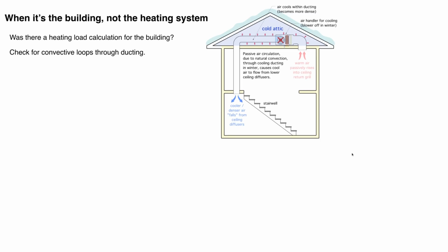And we're almost done here. When it's the building, not the heating system. We've been talking about potential issues with the heating system, but here's one that I actually learned a lesson on. It was a house. We did a nice radiant floor system for this house, a 2-story house, had an air handler for cooling up in the attic. This ducting was sort of insulated. It wasn't like R30, it might've been R5.